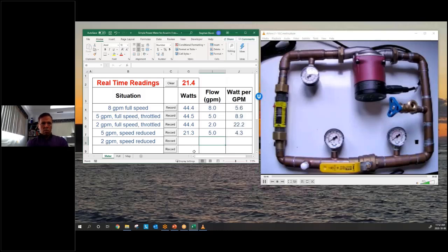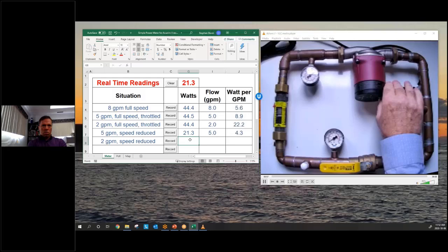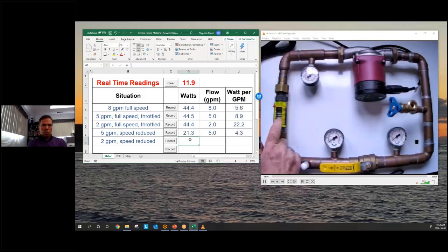Okay, let's try it again. We're going to drop now to 2 gallons a minute. So I'm going to set the pump down to 2 gallons a minute, right down here. I'm going to enter the flow here. And now we're sitting at 6.2 watts. So your choice: you can get 2 gallons a minute with the valve, or you can get it with speed control.